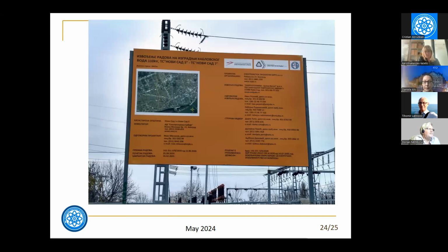At the end, I wish to mention that in 2022, the first underground 110 kilovolt 3-phase cable system was put into operation in Novi Sad. It connects 2 power transformer stations in the city. The length of the system is about 400 meters and passes through densely populated parts of the city. In order to verify the results we calculated, now we will make some measurements to verify this calculated value, and that's the next step in our project.